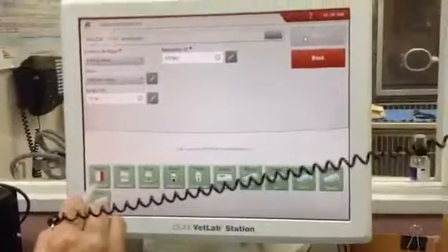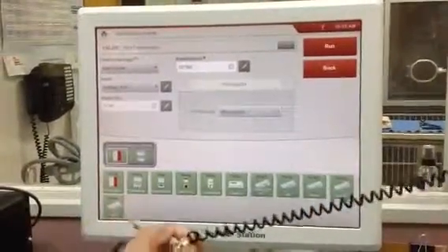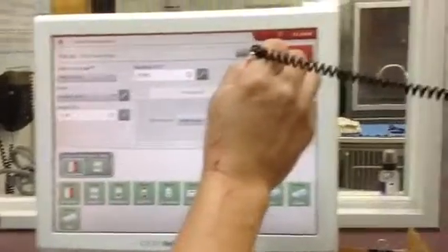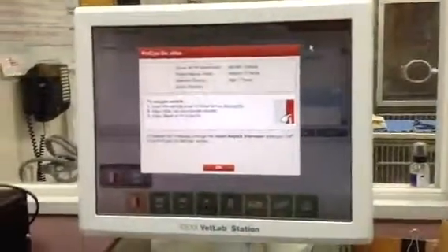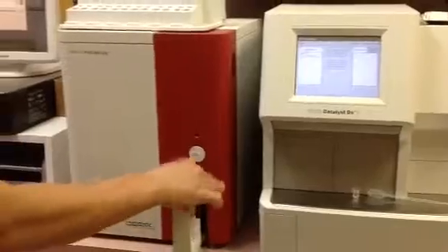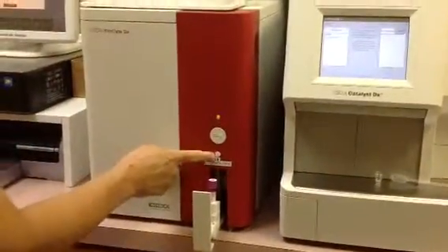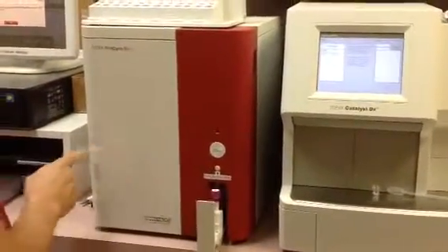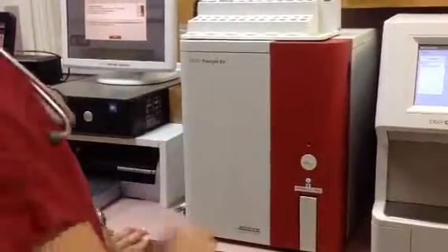We're going to use the ProCyte and the Catalyst. Then just tap Run. We go over here to this machine. We're going to use a fresh new sample — it is already in the rocker. Just open and close, close the door, and run the sample. This one takes approximately two minutes to run the CBC.